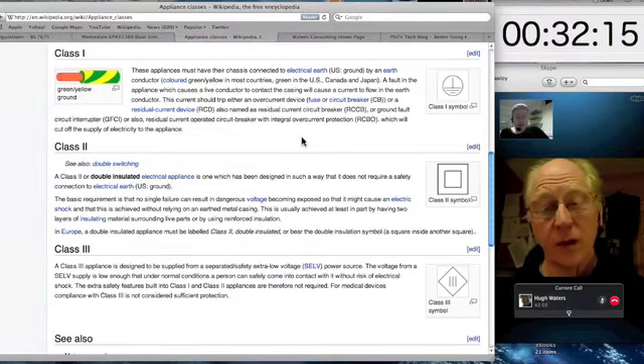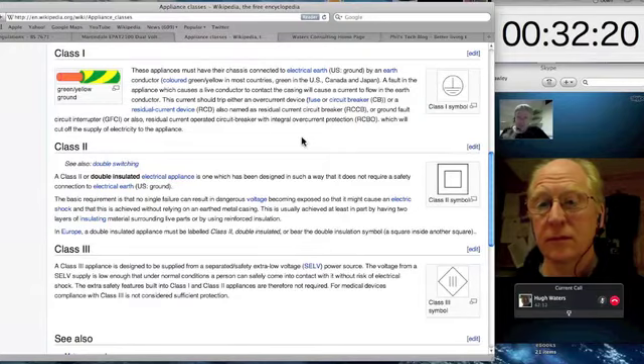Within the equipment, so long as there are two pieces of insulation, which can be the plastic box of the equipment and an air gap, then the requirements for certification and testing and the expense of building it are somewhat less, and you can call your piece of equipment a Class 2 piece of equipment. And it's why increasingly we're finding this in broadcast.